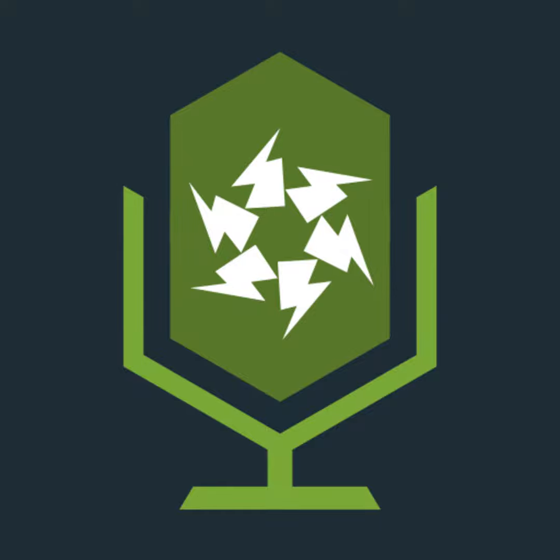I think that should say protective conductor current, such as it says below. But it's saying any earth leakage current to occur during normal operation. So, it's a bit weird. But okay. It will not cause unwanted tripping of the device. In order to avoid unwanted tripping by protective conductor currents and or earth leakage currents, maybe they're just throwing in both terms because they don't really know which one to use, the accumulation of such currents downstream of the RCD shall not be more than 30% of the rated residual operating current of the RCD.